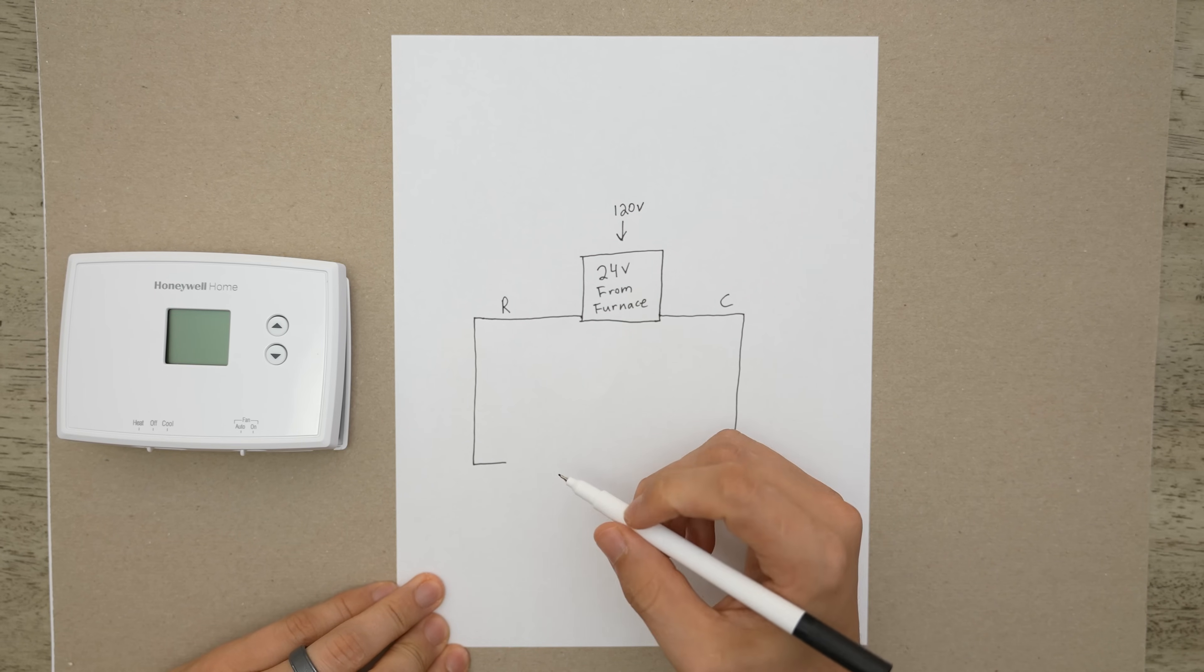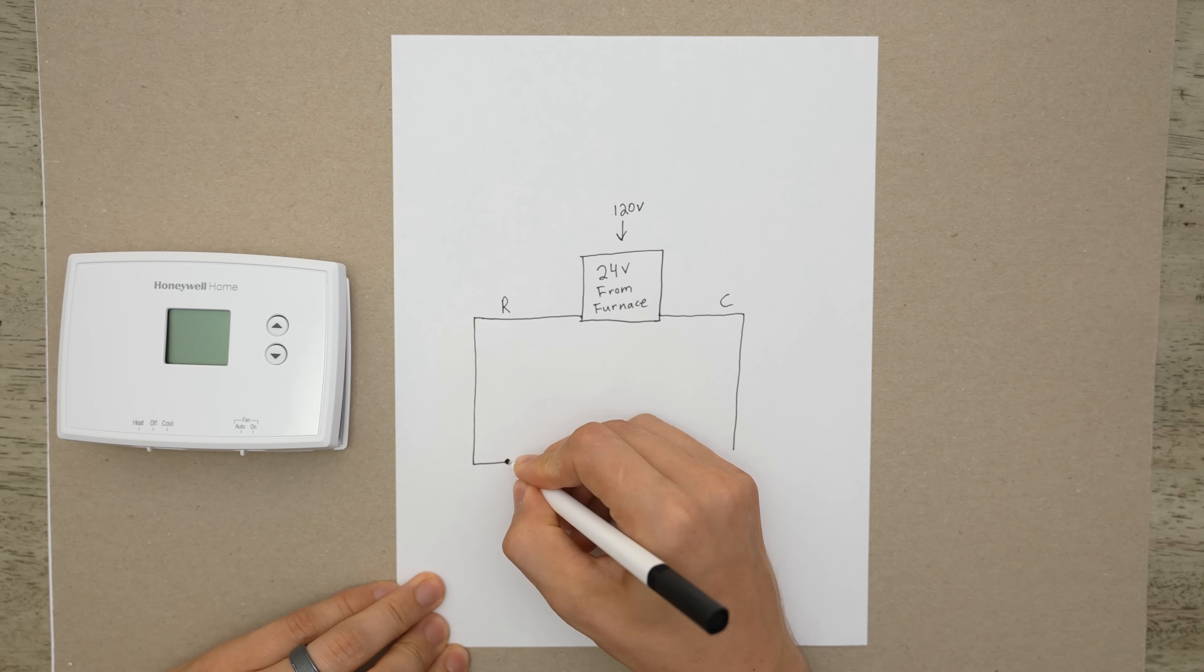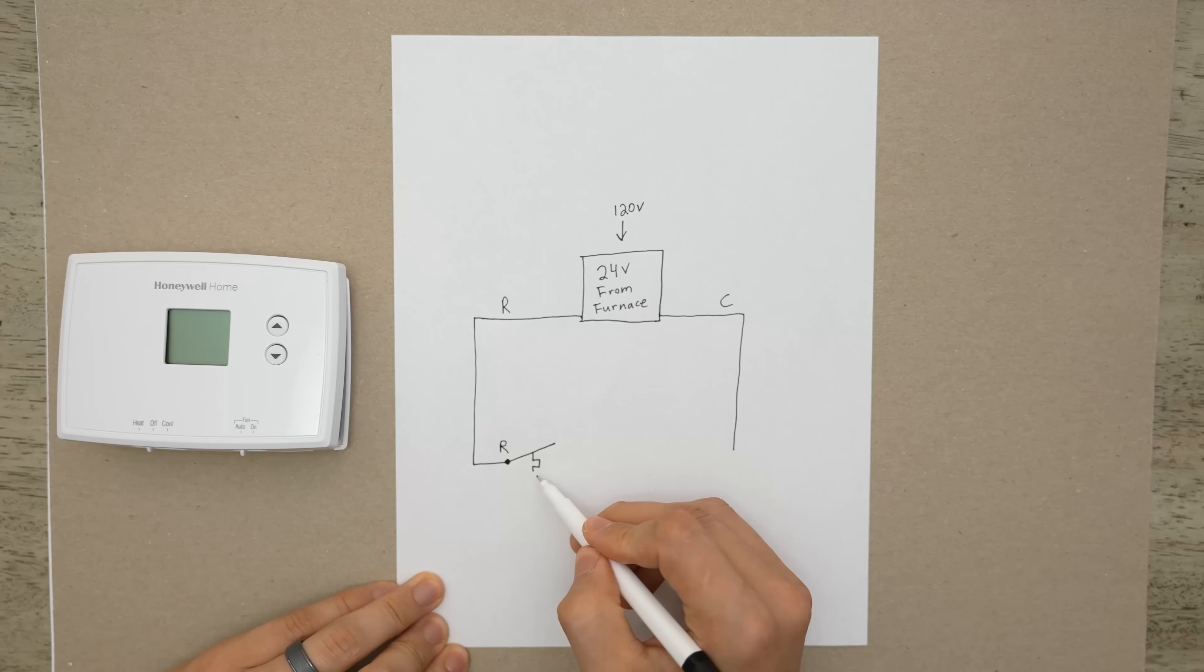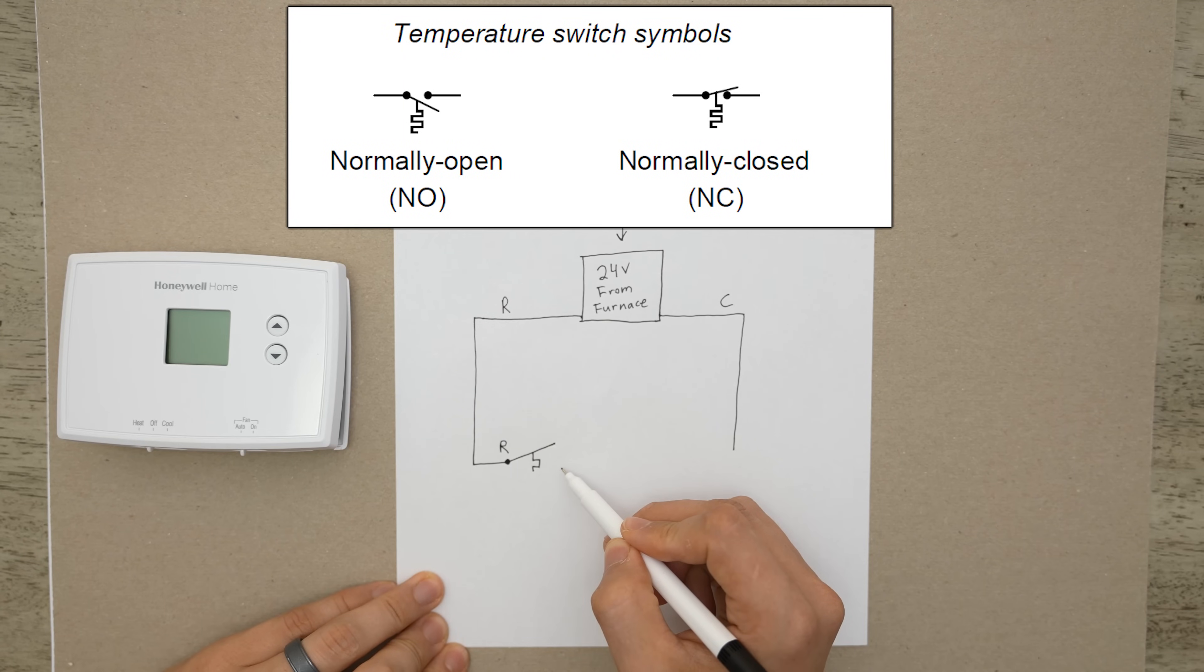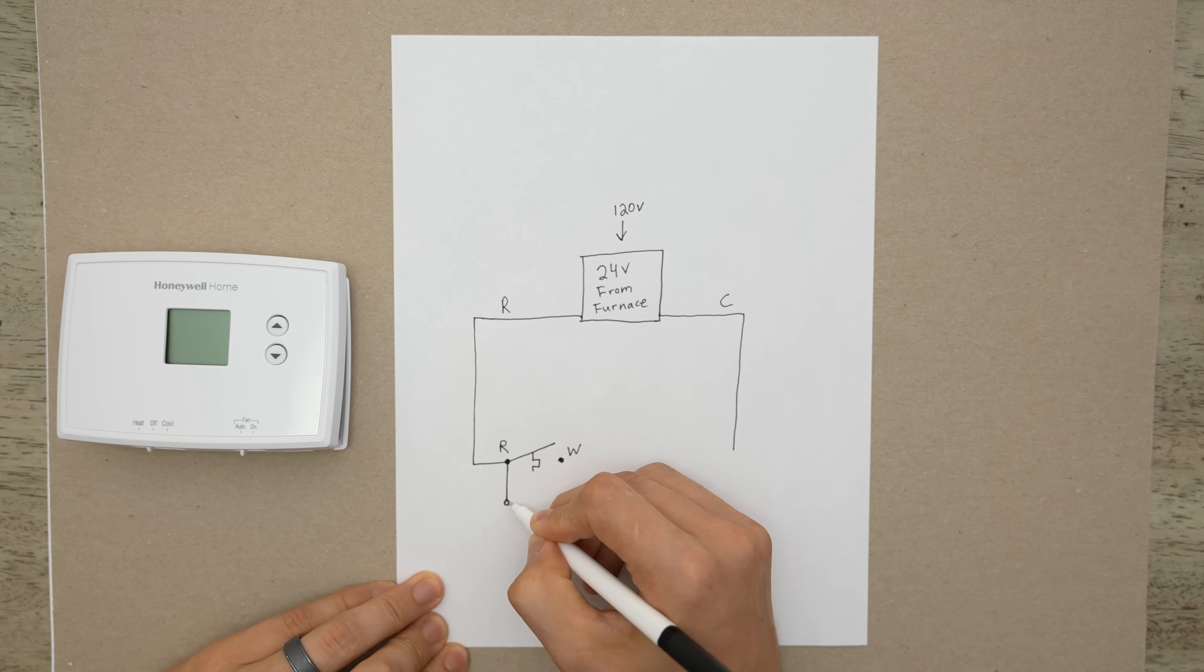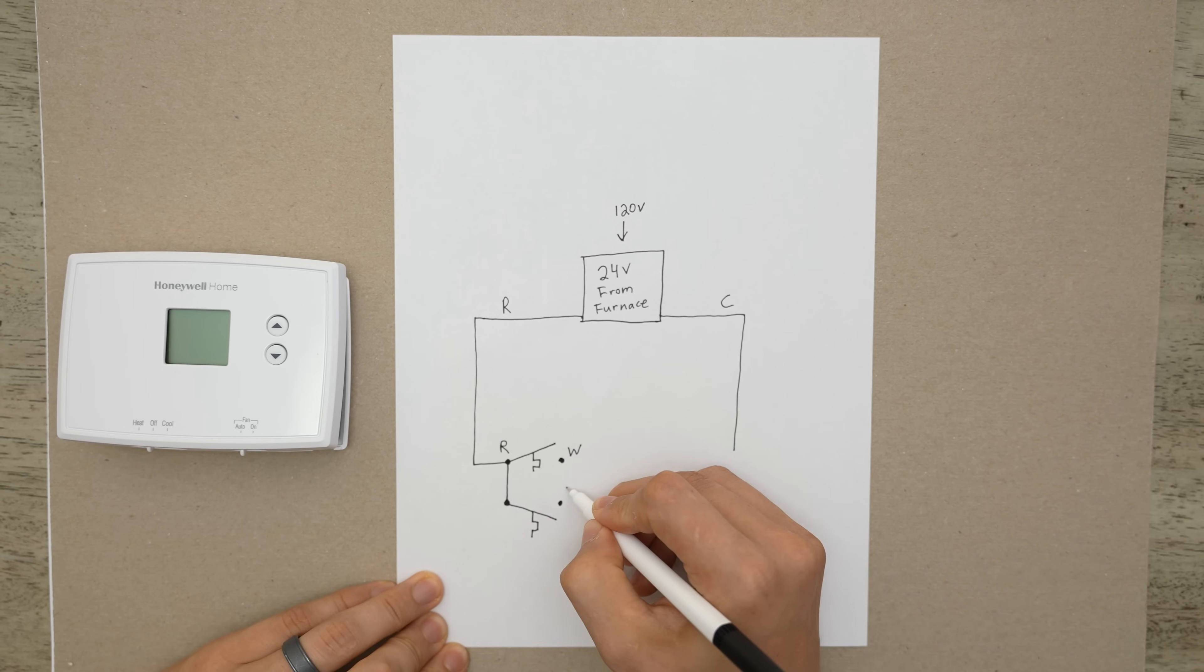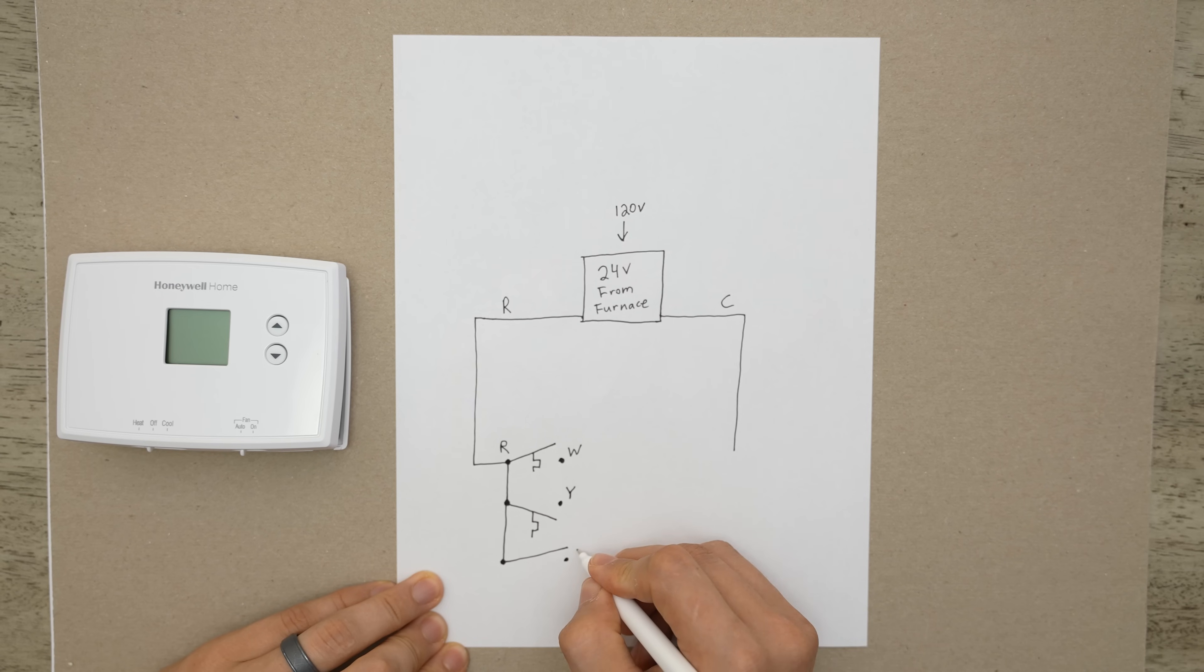And now let's go ahead and add the switches that are inside of the thermostat. So we're going to have an R terminal. This is going to be our first switch and it's going to look like this. Whenever you see a switch like this on a wiring diagram that is a temperature switch which means this switch goes up and down depending on the temperature. So that'll be our first switch. This one is going to be W. This is our heating. Let's draw our next switch. This one's going to look a little bit different. It's going to be coming from underneath it and it's also a temperature switch. This one is going to be Y for cooling. And then let's draw one more. This one is going to be a regular switch and this one's going to be G for fan.